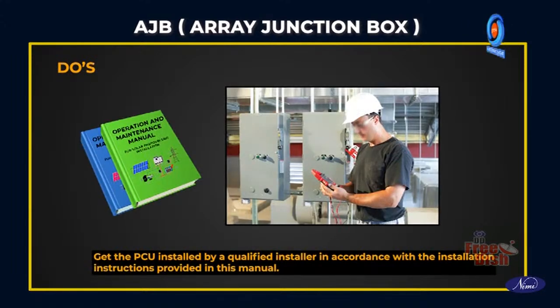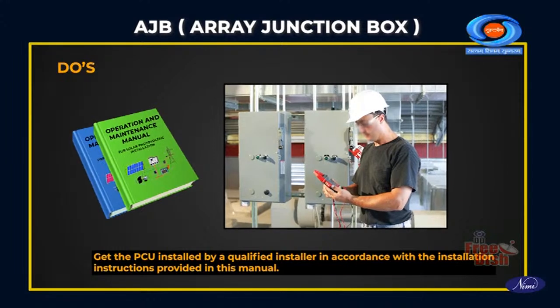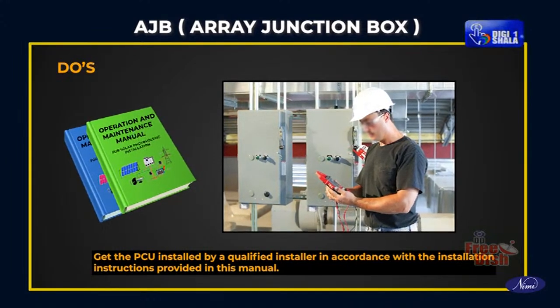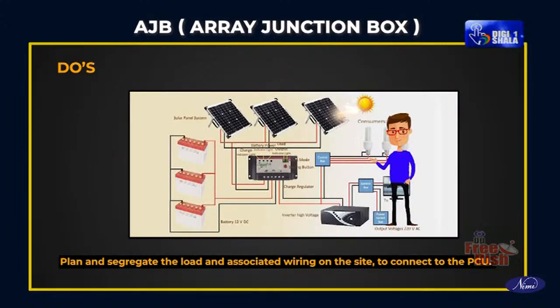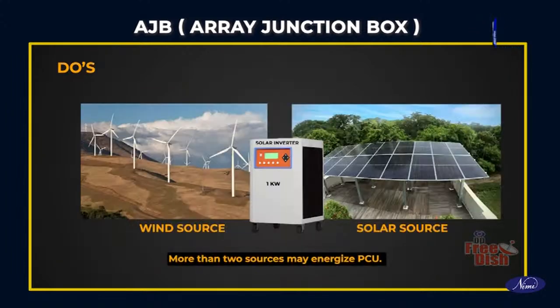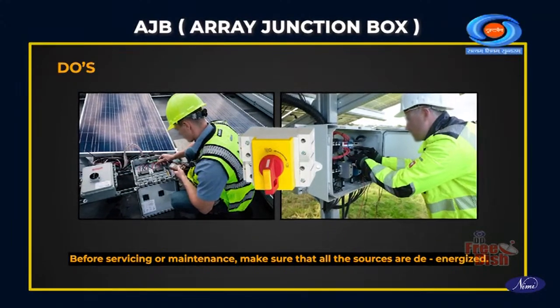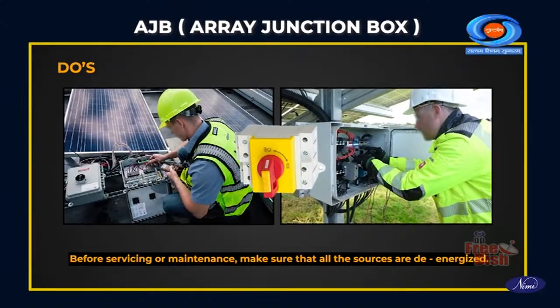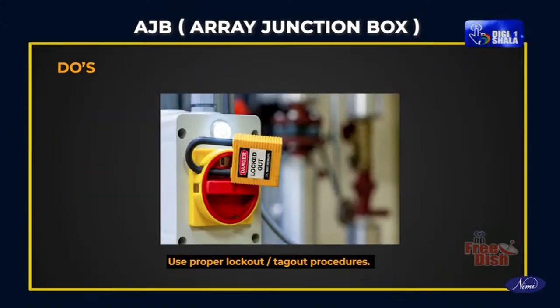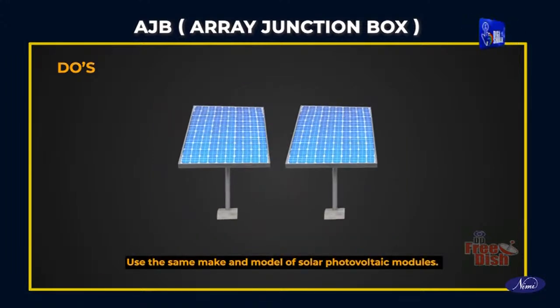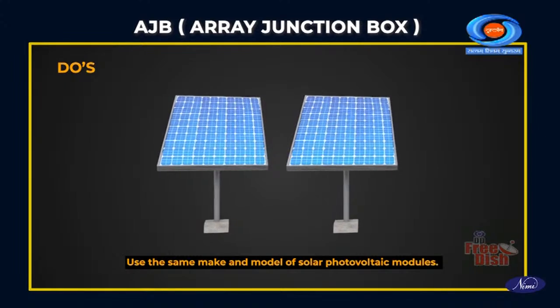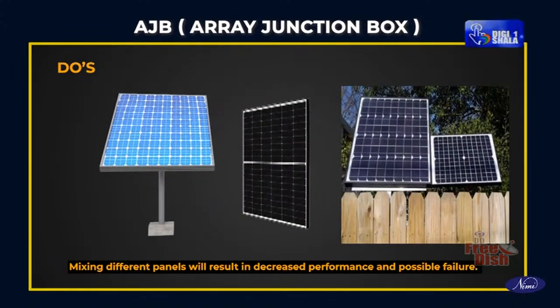AJB, array junction box. Do's: Get the PCU installed by a qualified installer in accordance with the installation instructions provided in this manual. Plan and segregate the load and associated wiring on the site. To connect to the PCU, more than two sources may energize the PCU. Before servicing or maintenance, make sure that all the sources are de-energized. Use proper lockout or tag-out procedures. Use the same make and model of solar photovoltaic modules. Mixing different panels will result in decreased performance and possible failure.